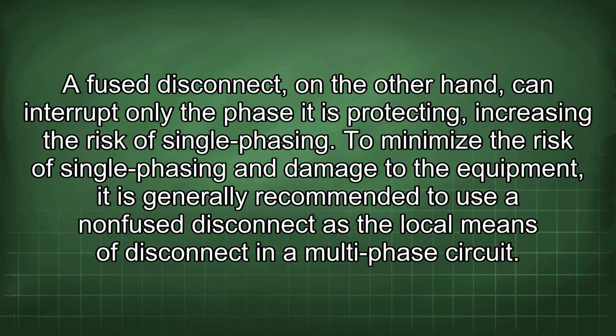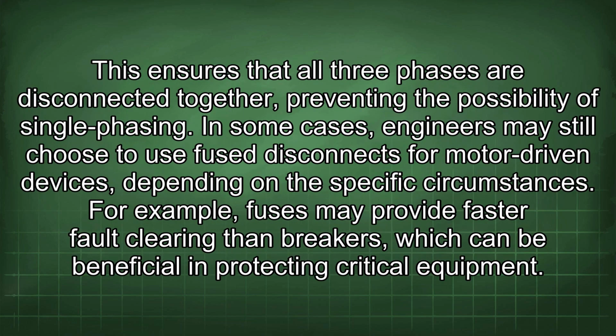A fuse disconnect, on the other hand, can interrupt only the phase it is protecting, increasing the risk of single phasing. To minimize the risk of single phasing and damage to the equipment, it is generally recommended to use a non-fused disconnect as the local means of disconnect in a multi-phase circuit. This ensures that all three phases are disconnected together, preventing the possibility of single phasing.